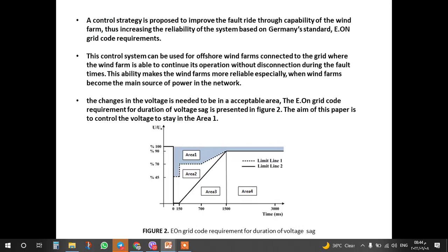A control strategy is proposed to improve the fault ride-through capability of the wind farm, thus increasing the reliability of the system based on the German E.ON grid code requirements. This control system can be used for offshore wind farms connected to the grid where the wind farm is able to continue its operation without disconnection during the fault times. This ability makes the wind farm more reliable, especially when wind farms become the main source of power in the network. The changes in the voltage need to be in an acceptable area.